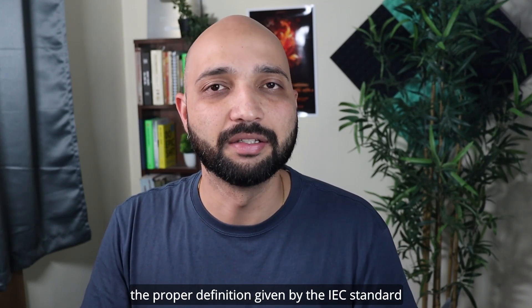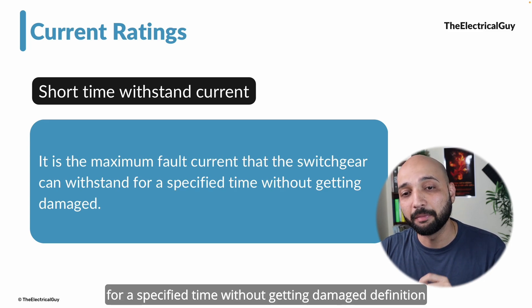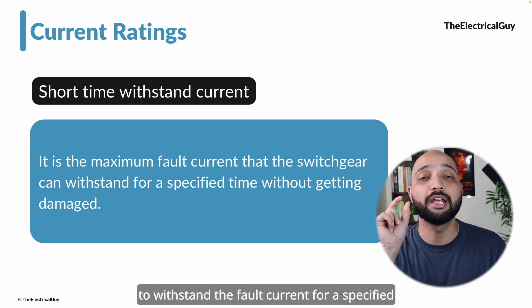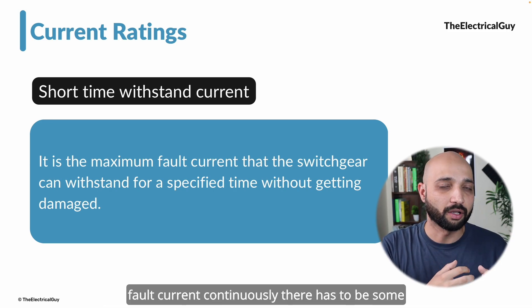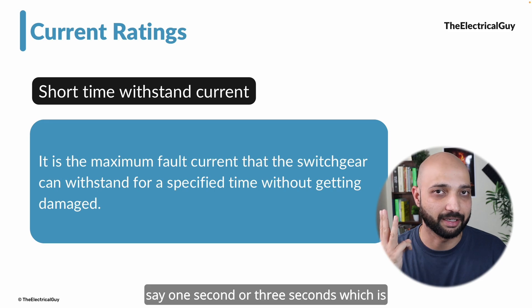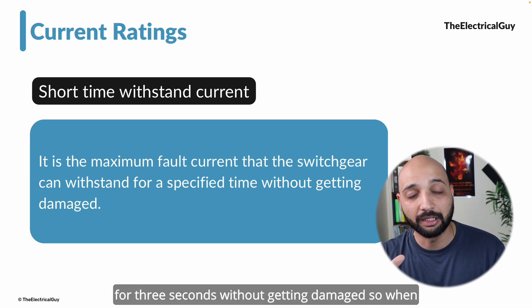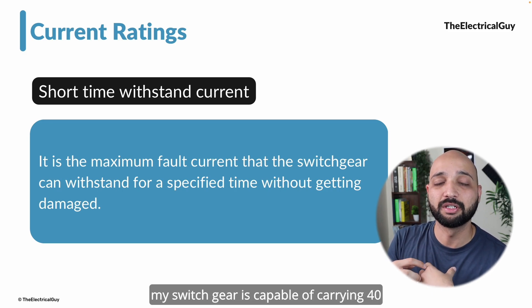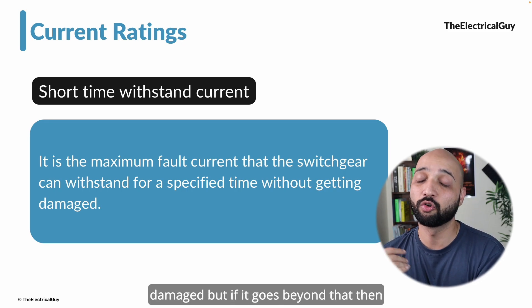The IEC defines short time withstand current as the maximum fault current that the switchgear can withstand for a specified time without getting damaged. It is the capability of the switchgear to withstand the fault current for a specified amount of time. We are not talking about continuous current carrying capacity — no switchgear is designed to carry fault current continuously. Again, the limitation is one second or three seconds, which are the standard values followed throughout the industry. When we specify 40 kA for three seconds, it means the switchgear is capable of carrying 40 kA for up to three seconds without getting damaged. Beyond that, we cannot guarantee.